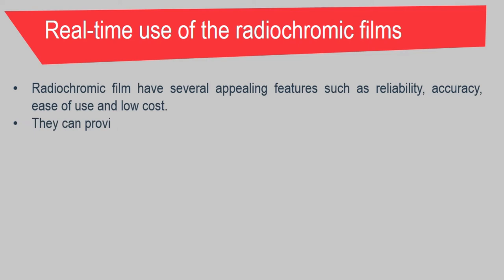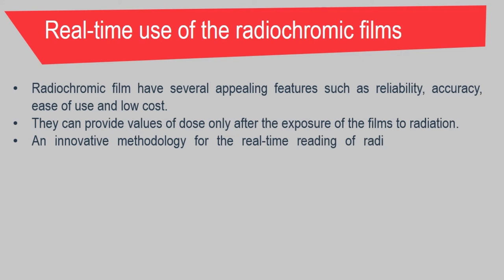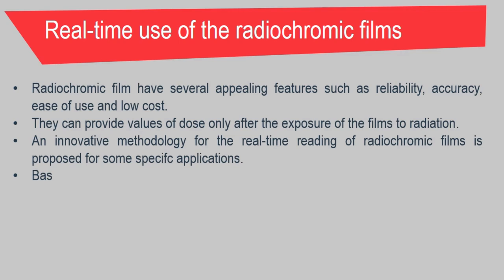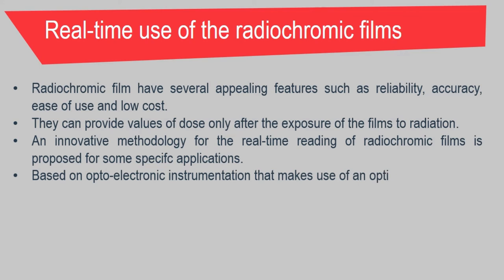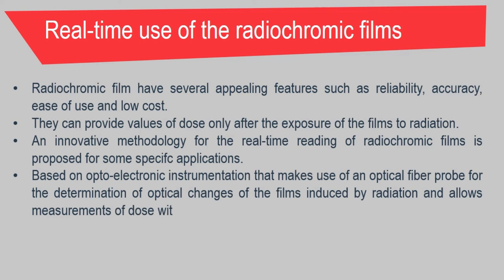The radiochromic film has several appealing features such as reliability, accuracy, ease of use, and low cost. They can provide dose information only after exposure of the film to radiation. However, there is an innovative methodology for the real-time use of radiochromic films proposed for specific applications. This is based on opto-electronic instrumentation that makes use of an optical fiber probe for the determination of optical changes induced by the radiation, and allows the measurement of dose with a high degree of precision and accuracy.